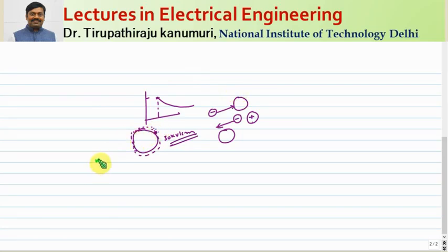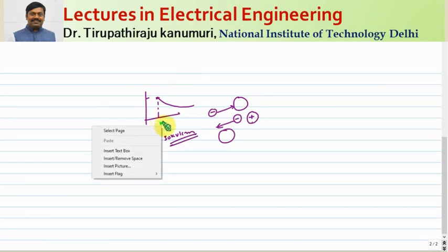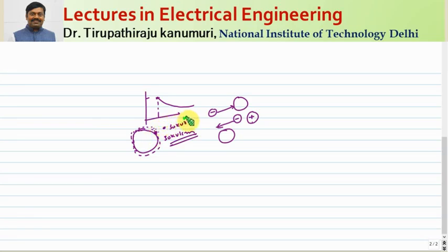So what is the solution for this? Let us assume the voltage is further increased to such a range that 30 kV per centimeter is coming at some distance far away from the surface of the conductor. Let us assume it is happening at this point. So at this point it is 30 kV per centimeter. Now what happens? The area between the surface of the conductor and the point where 30 kV per centimeter is coming will get ionized, because as it got ionized, it will also start acting as a conductor. As the particles came and accumulated on the surface of the conductor, they will contribute to your conduction process. As they are moving, they will be visible in the form of light.